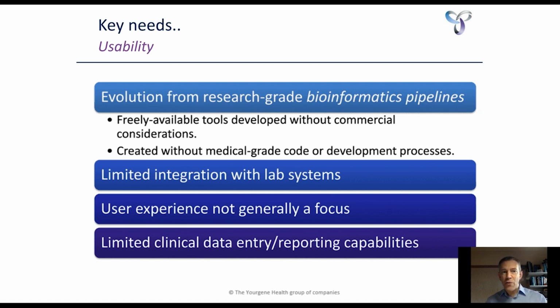And then also the other thing about usability is it does have an important interaction with safety. So ISO IEC 62366 is another standard in that area. And that's about designing user interfaces and user experiences to reduce the risk of errors and make sure that safety isn't compromised through misuse. Usually the outcome of risk analysis work and user panels, user focus testing, that kind of thing.